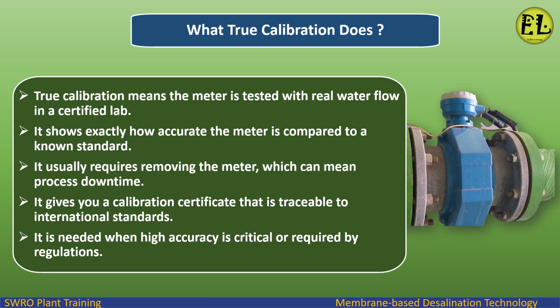What does true calibration do? True calibration means the meter is tested with real water flow in a certified lab. It shows exactly how accurate the meter is compared to a known standard. It usually requires removing the meter, which can mean process downtime. It gives you a calibration certificate that is traceable to international standards. It is needed when high accuracy is critical or required by regulations.